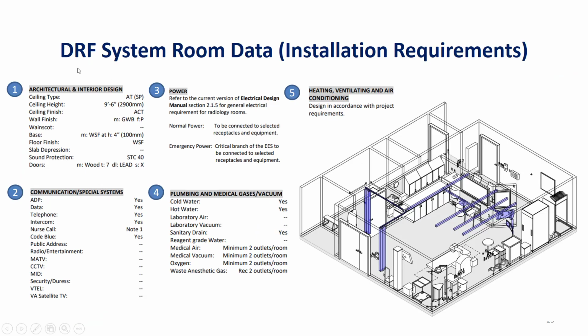In addition to the in-depth knowledge of the DRF system, we need to have a good, in-depth knowledge of the site requirements in order to install and operate the DRF system properly and safely. These requirements are summarized in a room datasheet. These requirements include architectural and interior design, communication and special systems, power, plumbing and medical gases, and finally heating, ventilating and air conditioning, known as HVAC system requirements. So to sum up, the installation requirements of the DRF system include the need for a UPS hospital source, lead shielding of the walls and doors, medical gases, oxygen, vacuum and medical air, special room height to allow the tilting movement of the table, as well as other requirements.